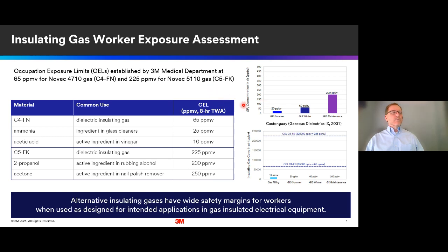But probably more importantly, how does that compare to what you would expect in a switchgear application? So the graphs on the right, for example, show measurements that were made on SF6 over the course of a year at indoor substations, and show varying concentrations of SF6 that could be found at the time of year and even during maintenance. Actually, all are well below 1 part per million. And then the lower right compares that relative to these occupational exposure limits, which have been determined to be the safe limit that a worker could be exposed to 8 hours a day, 5 days a week, 52 weeks a year throughout their entire working life. And you can see there's actually a very wide margin of safety between where the expected exposures could be from a typical gas insulated equipment installation and what's deemed to be a safe level for workers.